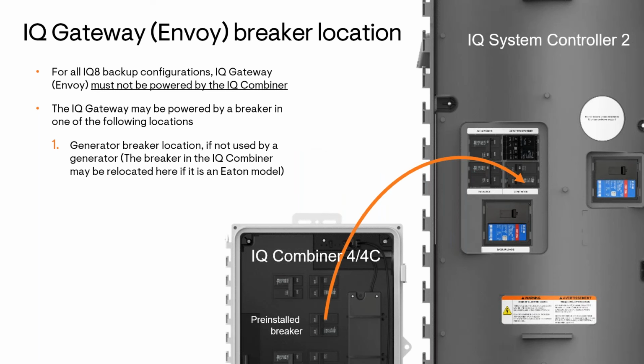Now there is a breaker, of course, that's inside the IQ combiner that's normally used for the gateway. However, to be installed in the system controller 2, it must be an Eaton breaker. And the breaker that's in the combiner may or may not be an Eaton breaker. My understanding is that sometimes it is and sometimes it isn't. So if that breaker is Eaton, it can be moved over to the generator slot, but if not, then you would have to sell them an Eaton breaker to be installed in the generator slot.